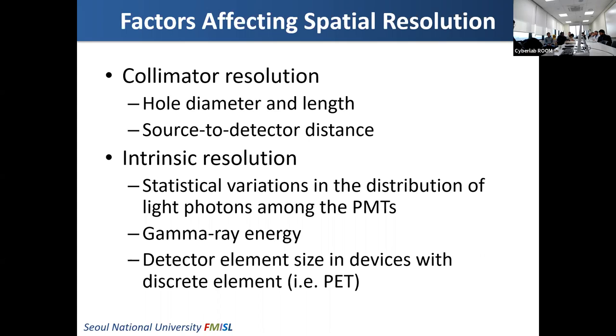In terms of intrinsic resolution, high energy is better because high energy generates more scintillation photons. With a larger number of scintillation photons, we can have better spatial resolution.